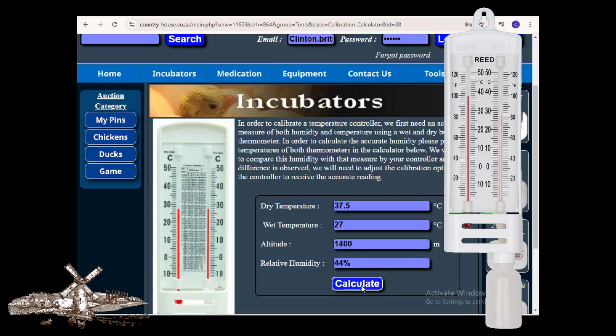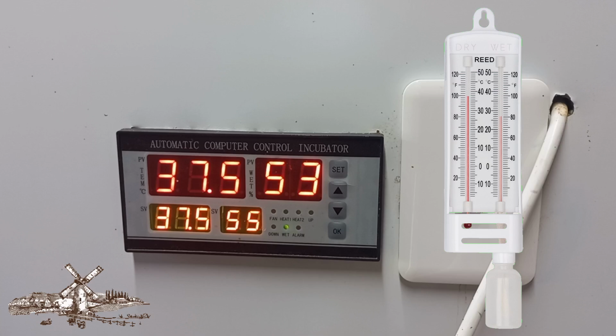And so what I need to do is adjust my controller's humidity measurement to go from 55 down to 44%. Now, in order to do that, I need to subtract 11% off the current humidity measurement on my controller. And if I do that correctly, I would expect the humidity measurement to drop down to 44%.